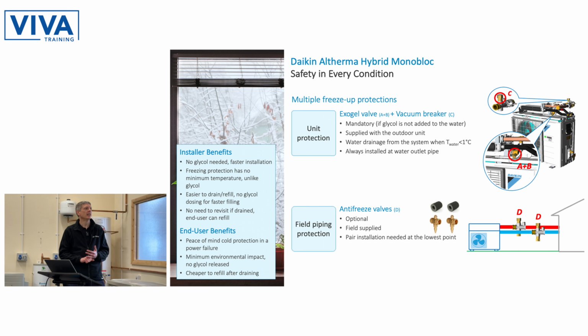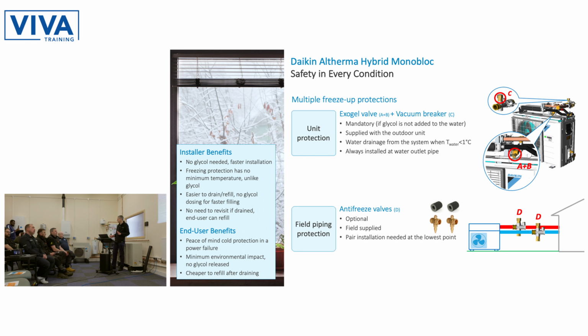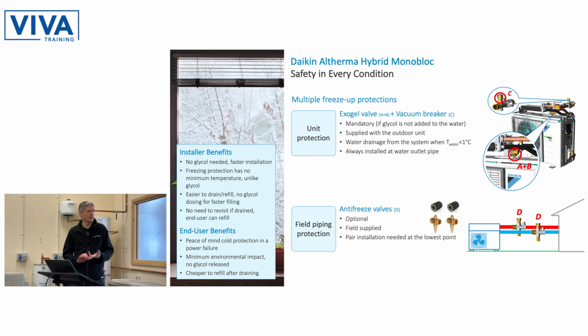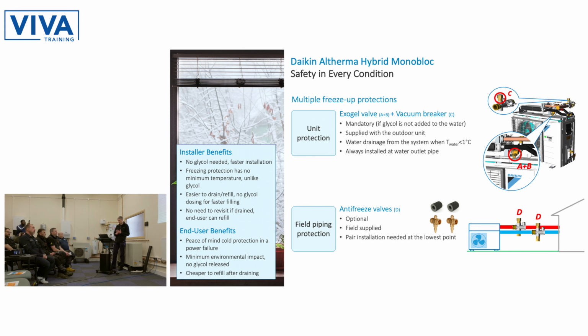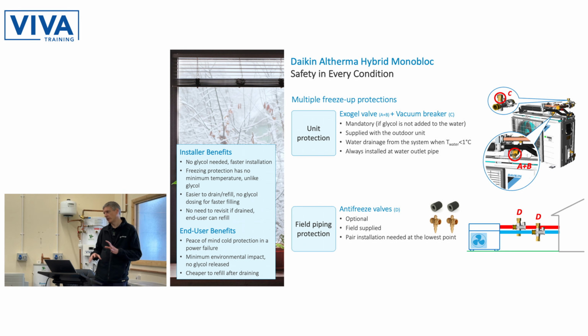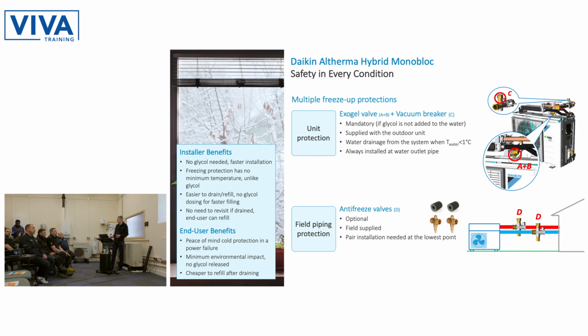And what we're saying instead is install antifreeze valves. So similar to the exogel valve protecting the heat exchanger in the heat pump, and they go on the lowest point of the pipework between the heat pump and the inside of the property. They're quick and easy to put in, 5-10 minutes as part of your pipework install. They're insulated. They've come with their own jacket. And when they sense that they're effectively monitoring the water temperature inside them, and when that gets down to -3, it will start dribbling water out, in order to drain the water out of that pipework. When it comes back to 4 again, it will close, and you can refill the system again. Obviously, it might never happen in the lifetime of the heat pump.